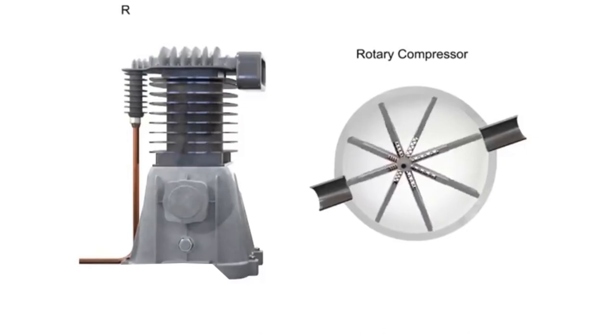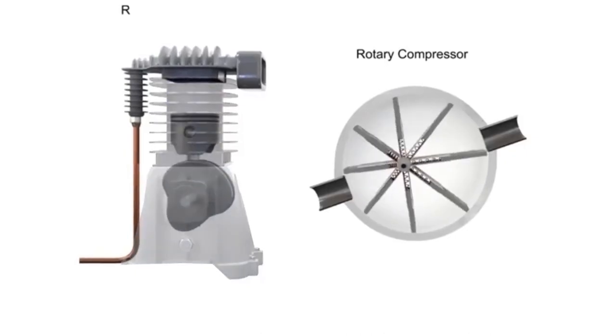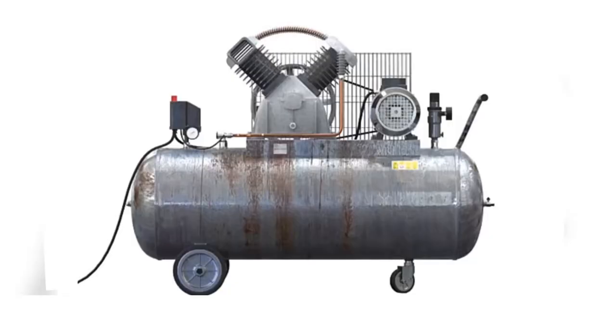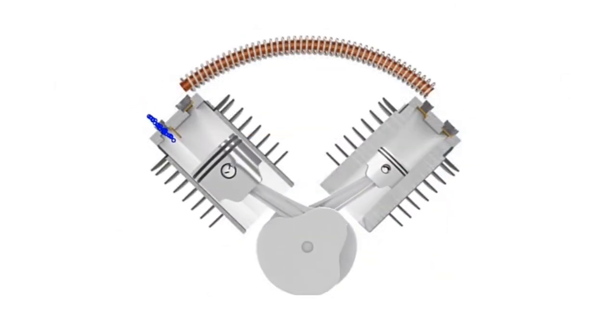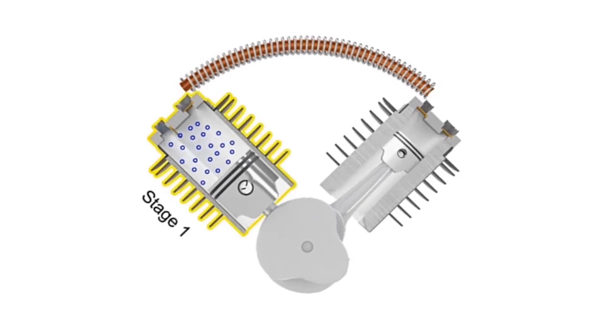But what happens in a two-stage air compressor? Let's find out. Two-stage compressor. Unlike the single-stage compressor, the compressed air never goes in the receiving tank but rather goes through another round of compression via the second piston before it is finally directed to the storage tank.